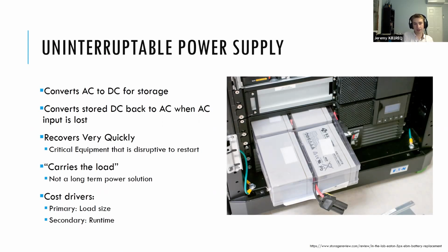A term you'll hear a lot when talking about UPS is they carry the load. So what that means is they're not a long-term power solution. They're designed to carry your AC power until something long-term can kick in. Now, that doesn't mean that there aren't long-term UPSs. There are. They're just very large and very expensive, and I would say more on the atypical side. Usually your UPS is a transitionary backup power source that absorbs anything that's, say, momentary, you know, any quick power losses, any kind of blips in your utility power, up through several minutes to several hours, depending on the load and the size of your UPS. But if you're getting into days of power outage, it's hard to rely on a UPS, again, unless you have a very large solution.